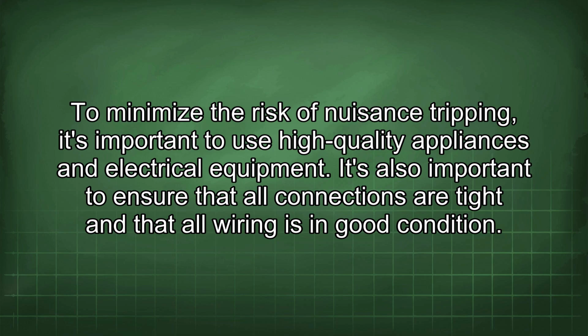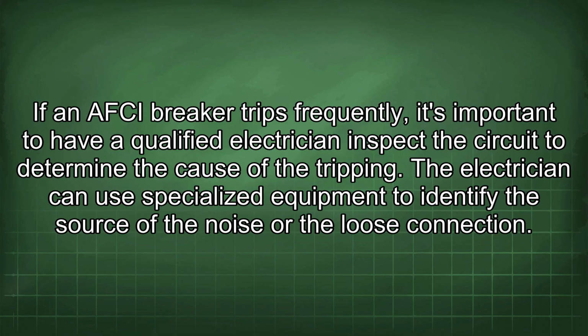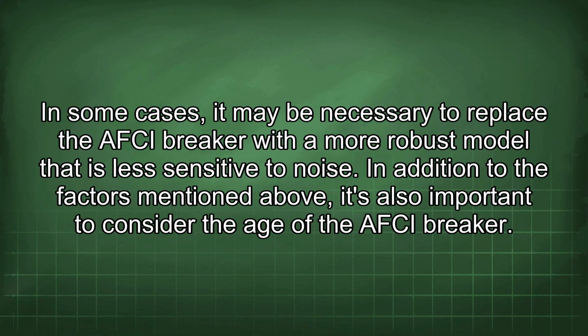To minimize the risk of nuisance tripping, it's important to use high-quality appliances and electrical equipment. It's also important to ensure that all connections are tight and that all wiring is in good condition. If an AFCI breaker trips frequently, it's important to have a qualified electrician inspect the circuit to determine the cause of the tripping. The electrician can use specialized equipment to identify the source of the noise or the loose connection. In some cases, it may be necessary to replace the AFCI breaker with a more robust model that is less sensitive to noise.